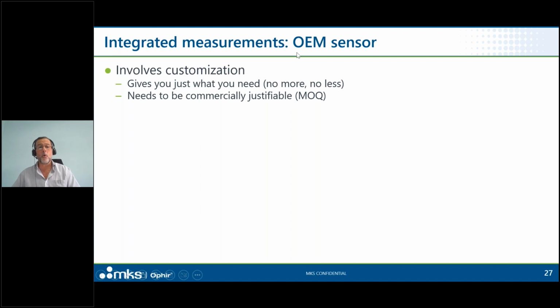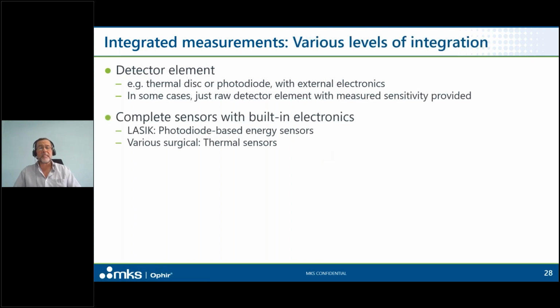If one goes the route of an OEM solution, there are all sorts of levels of integration that one might choose for the solution that one wants to implement. Maybe starting just with a raw detector element with or without electronics. In some cases, particularly when we're talking about large quantities, and important to emphasize, advanced users, there are customers who use just the raw thermal disk or just the raw photodiode element, possibly with the measured raw analog sensitivity provided, and that is the calibration that we would provide such customers for their sensors. And all the way up past detectors with built-in electronics tuned to a particular sensitivity or digital interface, all the way up to complete sensors, complete instruments with built-in electronics, and all sorts of stuff in addition.